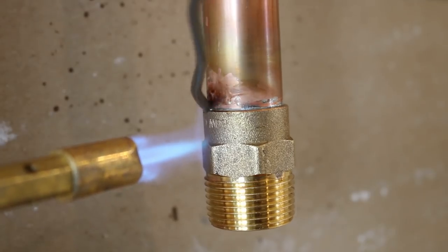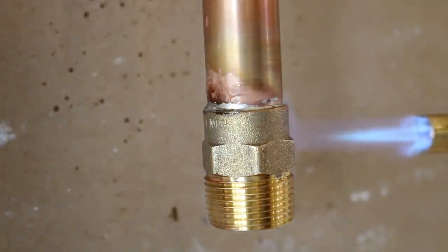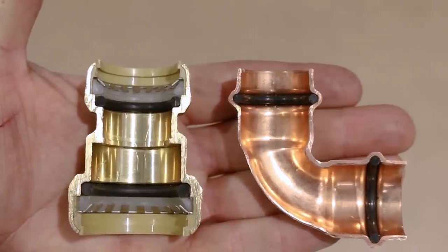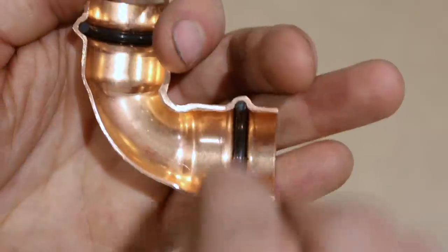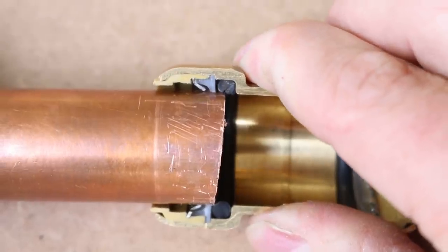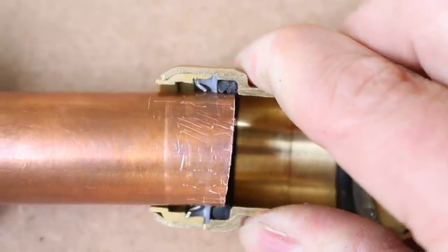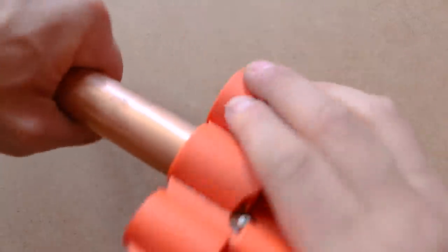If you're soldering for example, the outer edge doesn't necessarily need to be deburred. But if you're using SharkBite or ProPress fittings which rely on an o-ring to seal, the outer edge must be chamfered for it not to damage the fragile o-ring upon insertion. SharkBite actually sells a deburring tool just for this.